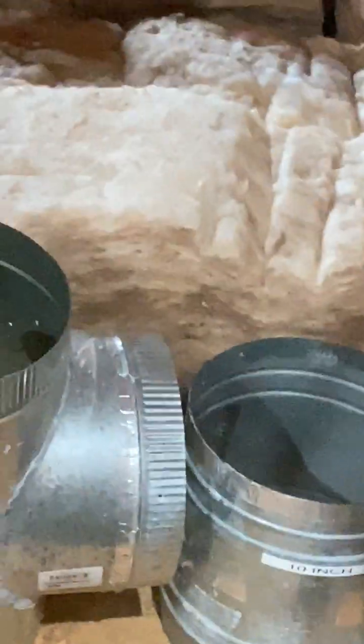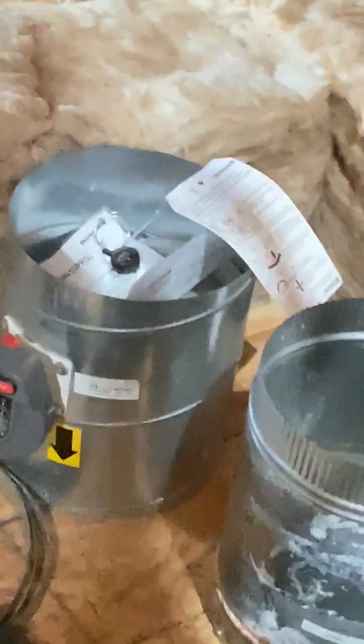So anyway, those are the zone control valves. I have them on the returns of 2 zones, as well as the ones controlling the actual blower, cool, or heat. Those are the zone control valves. I have, as I said, it's not hard to replace these yourself. I have a collection over here of various pieces. They're sets. That is a bypass damper, and in certain cases, HVAC people will tell you that there's a certain pressure that you're going to get in your system based on the suction of the blower and how big your ductwork is, and so on and so on.